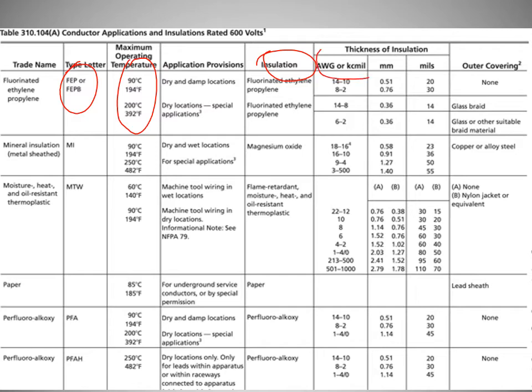This is the AWG, American Wire Gauge. This is the size of that gauge in millimeters, and this is the size in mils, and this is bare wire. As we go along, you see this list in the book, you can go through it. It tells you all those specifications. For example, this one is for dry and damp locations. This is for dry and wet. So some of them are not supposed to be in wet locations and so on.